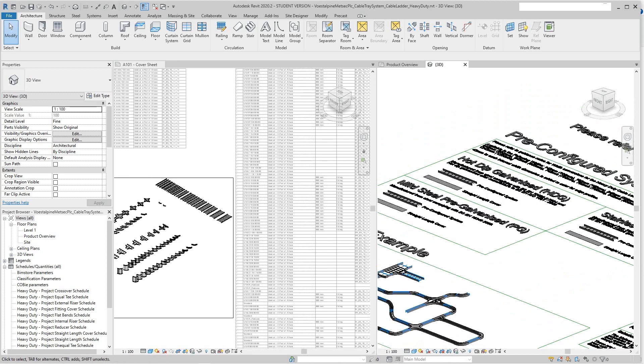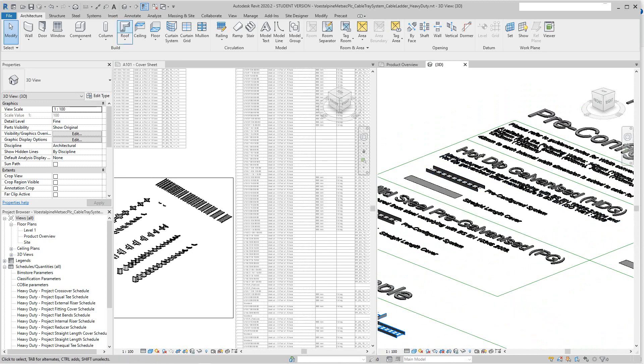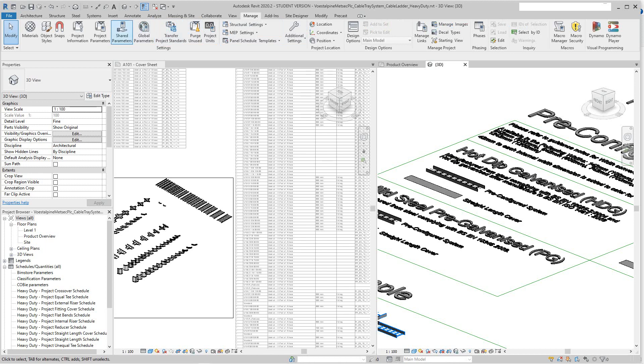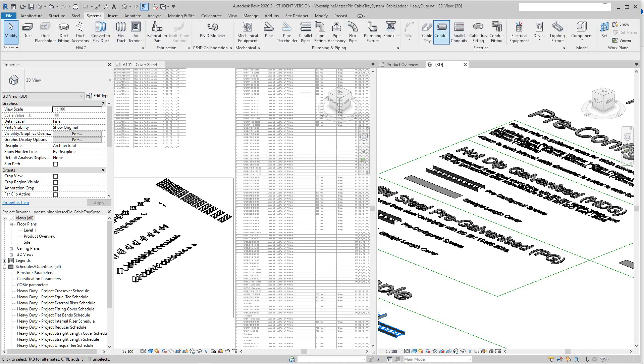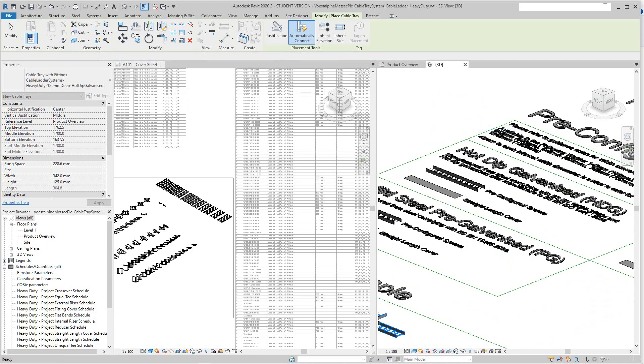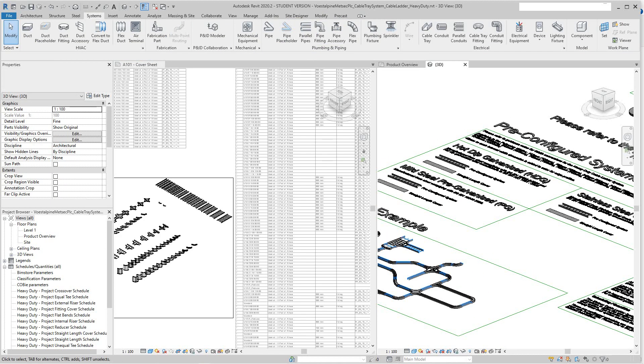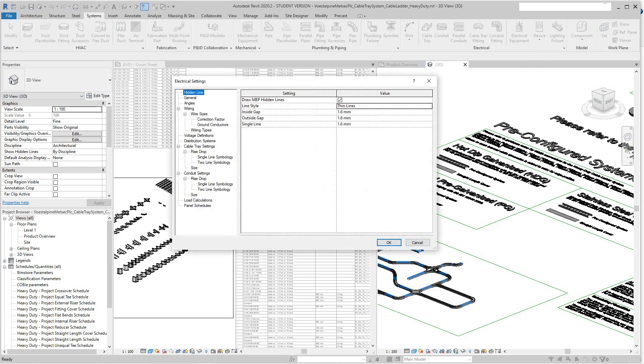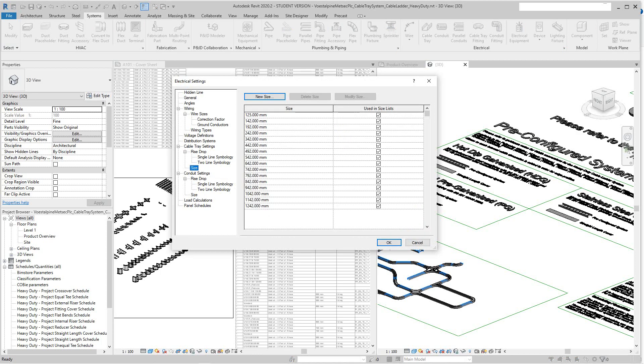What they did here — if I go into the Systems tab, on the cable tray, these are the base settings that they use. They use this 342 here for the ladder, and that should really be a 300. If I select this arrow right here and go down to cable tray settings, go to size — this is what happened: they changed all of the sizes in these cable tray to match up with their families.